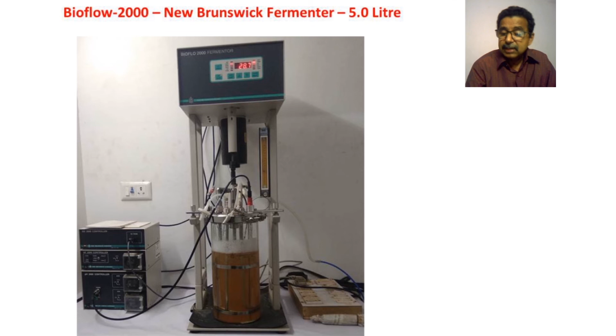It is nothing like a beaker, a 7-liter unit, where everything inside is connected through a top flange. There is a top stainless steel plate from which the pH electrode, the temperature electrode, the antifoam electrode, and the dissolved oxygen electrode are connected. This one, the SS one, is the dissolved oxygen electrode. So all electrodes are connected from the top. This is the control unit of the BioFlo 2000 fermenter, and in this control unit you can increase or decrease whatever data. You need to feed the data, then start the fermenter, and the entire control unit takes care of temperature, pH, and dissolved oxygen. Three things are controlled by it.